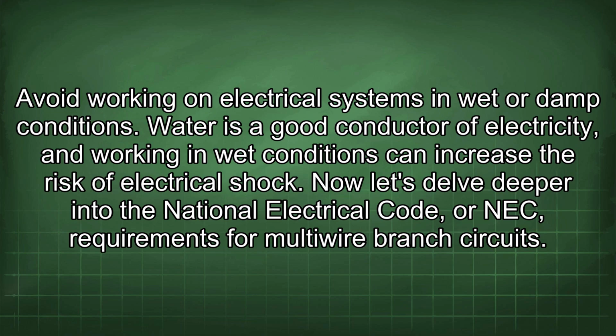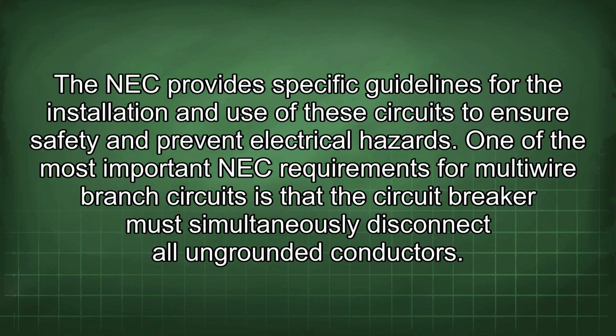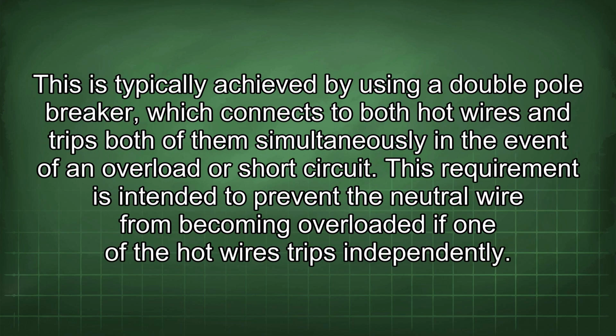Now let's delve deeper into the National Electrical Code, or NEC, requirements for multi-wire branch circuits. The NEC provides specific guidelines for the installation and use of these circuits to ensure safety and prevent electrical hazards. One of the most important NEC requirements for multi-wire branch circuits is that the circuit breaker must simultaneously disconnect all ungrounded conductors. This is typically achieved by using a double-pole breaker, which connects to both hot wires and trips both of them simultaneously in the event of an overload or short circuit.